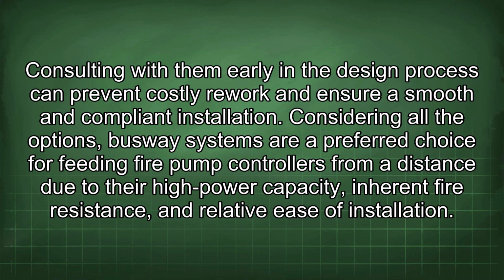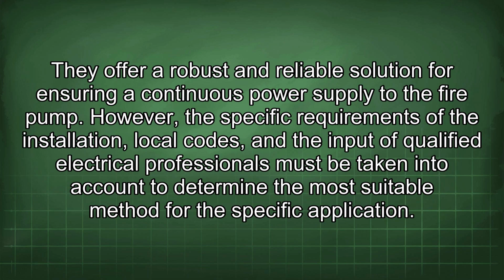Considering all the options, busway systems are a preferred choice for feeding fire pump controllers from a distance due to the high power capacity, inherent fire resistance, and relative ease of installation. They offer a robust and reliable solution for ensuring a continuous power supply to the fire pump.